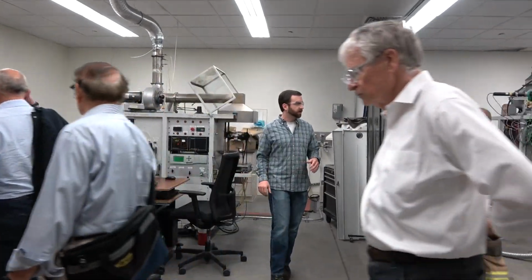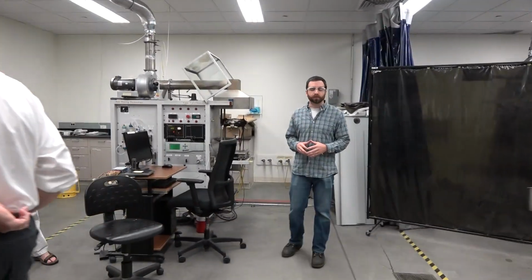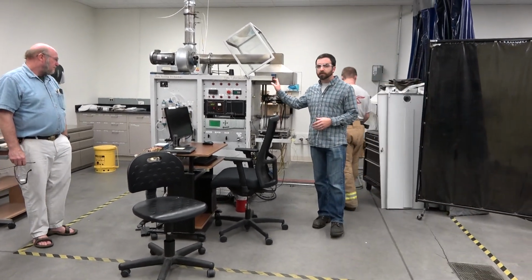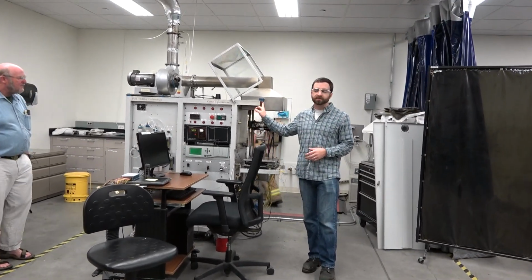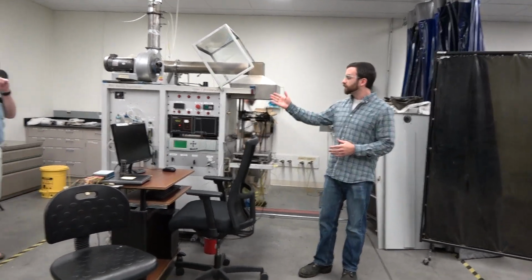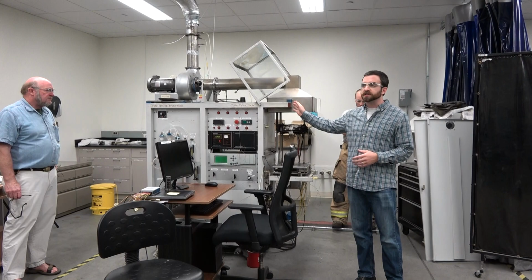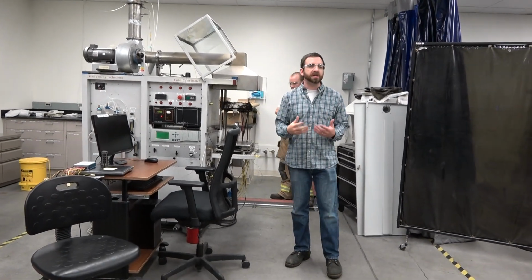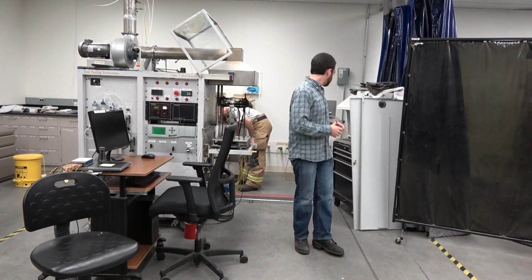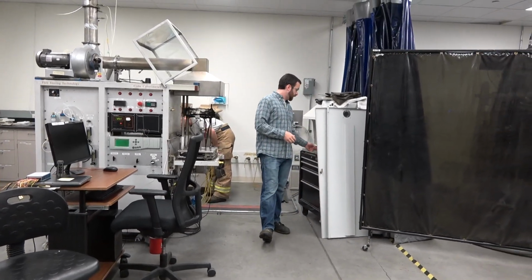Instrumentation and diagnostics that we use for material characterization. One of the baseline frontline apparatus that we have in fire science is the cone calorimeter. As the name would imply, this is a piece of equipment that's used for measuring energy output.